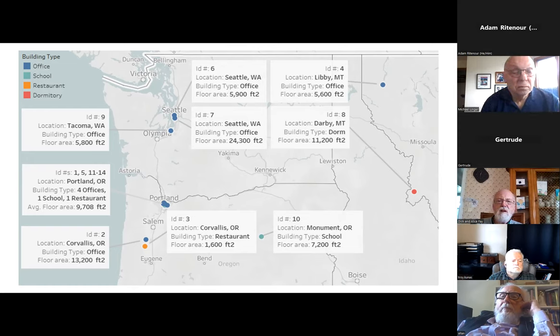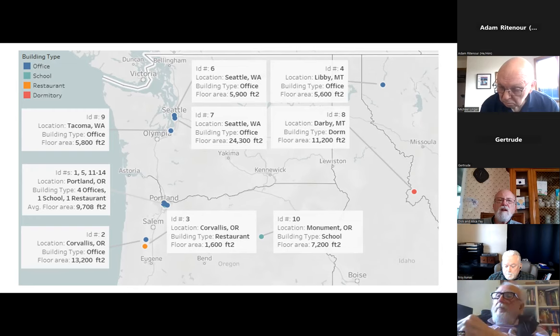Of these 14 projects, 9 of them were offices, 2 were schools, 2 were restaurants, and 1 was a dorm. And these buildings ranged in size from 1,600 square feet up to 24,000 square feet. So a good spread of commercial building size there. And what were these existing systems? 8 of these systems were packaged gas rooftop units, which is very common in small commercial Northwest buildings. Another 3 were electric rooftop units. And the last 3 were rural sites with residential style furnaces.